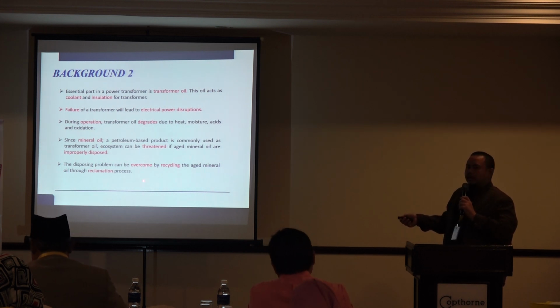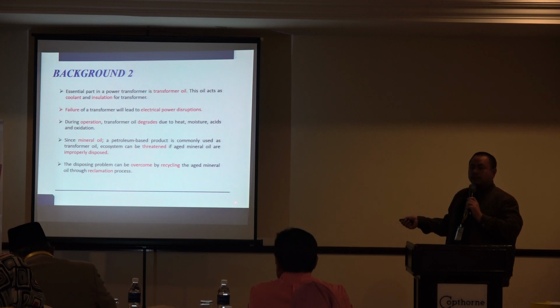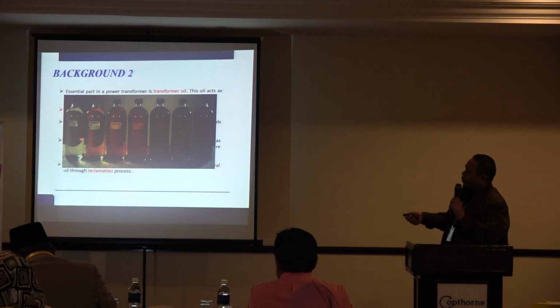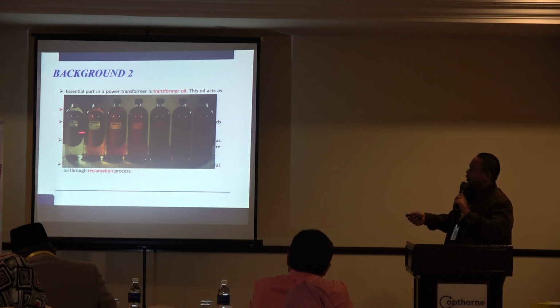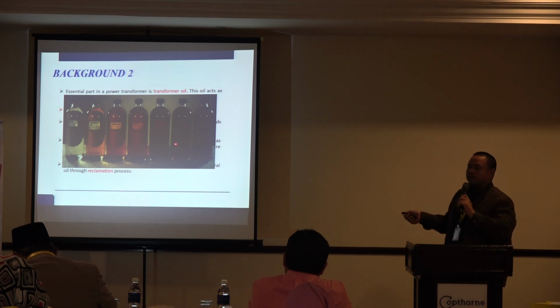So for maintenance of the transformer oil, they apply recycling of the mineral oil, which they call the reclamation process. This is the oil we have. Transformer oil is actually like plain water, a very bright color. But after high aging and thermal stress, it changes to a black color. If it is black, the acidity inside the oil will be higher, and higher acidity means it is prone to reduce the electrical integrity of the power transformer itself.